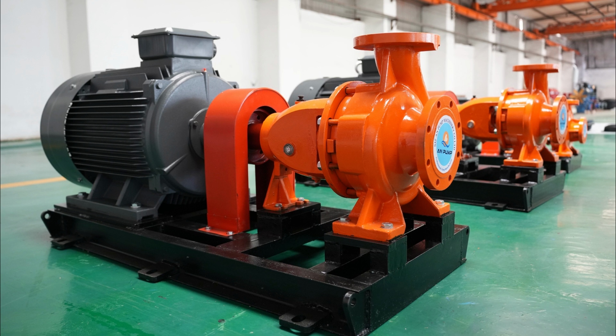We're talking pressure gauges, temperature sensors for both the fluid and the bearings, flow meters to measure the actual flow rate, vibration sensors to catch any red flags, and power meters to keep track of energy use. All this data can be fed into a control system so you can keep an eye on things from afar, make adjustments as needed, even do an automatic shutdown if something goes haywire.